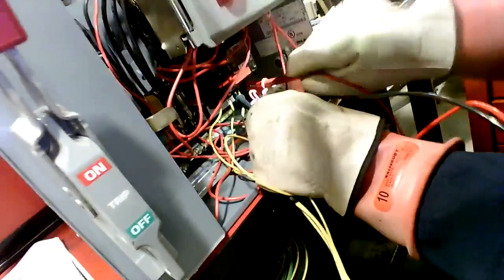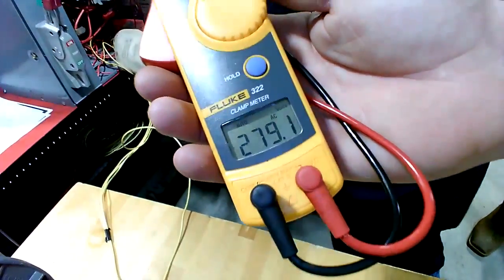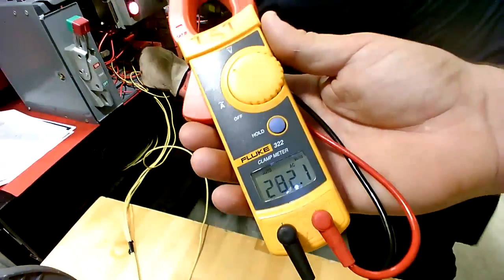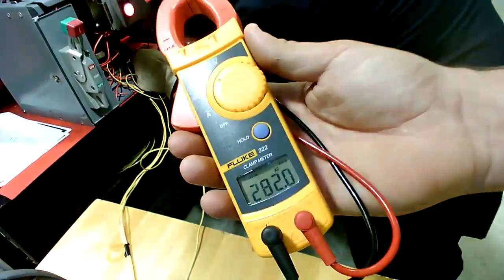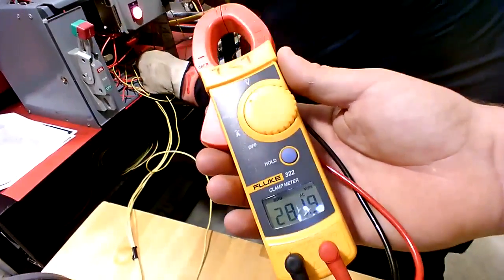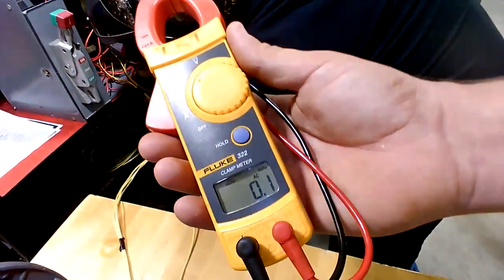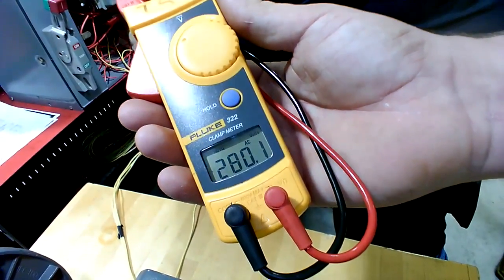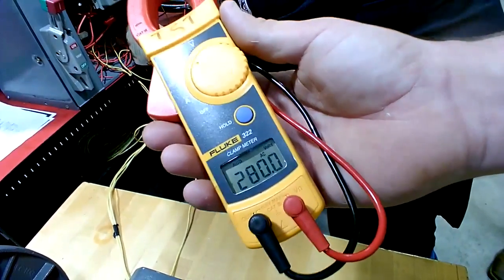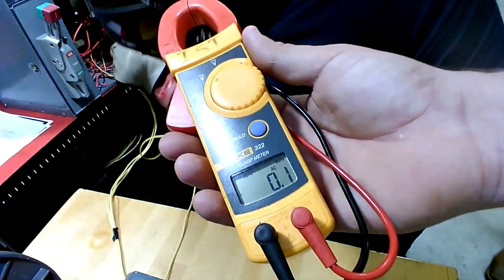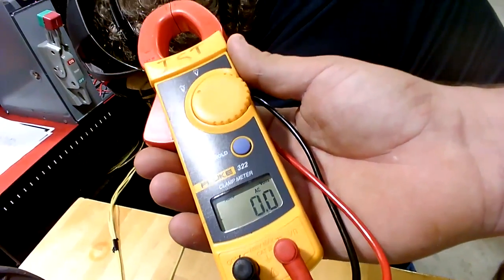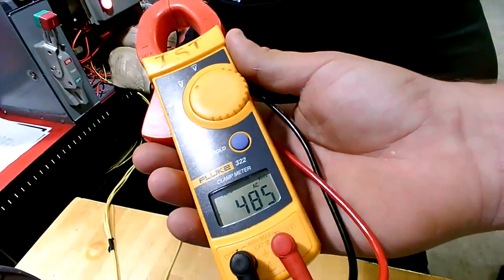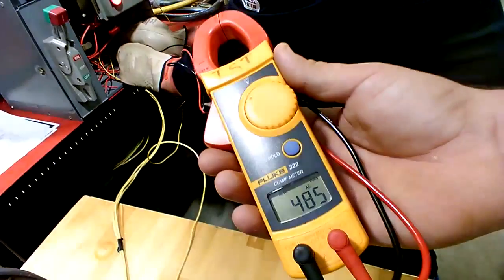Okay, now we're going to go from each phase conductor to ground. I've got a ground connection right here on the outside, and we're going to go from T1 to ground. 279. We're going to go from T2 to ground. 282. Okay, 277 is nominal, but that's a middle low number. Okay, we're going to go from T3 to ground. 280. Right. So we're actually a little on the high end, higher than 277, and that's because phase to phase it's actually higher than 480. I go back T1 to T2, and you're reading 481. You're reading about 5 or 6 volts higher than nominal. So that also means that your phase to ground readings are going to be a little bit higher too.